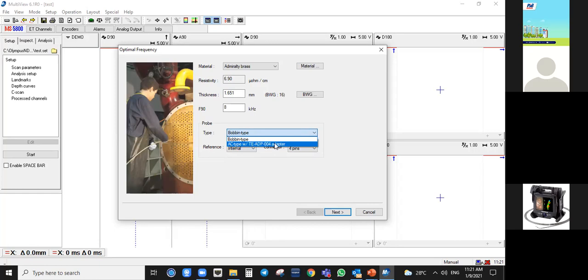So it's a combination. That's why it can detect circumferential crack on finned copper tubes. Oh, okay. Okay. So this one, this AC type probe, it has two connectors. So one connects with the bobbin and one connector with the pancake coil. And then you need an adapter so that the adapter will plug into this 41 pin. Okay, okay. So in your case, you have only bobbin type and then the connector is 4 pin.